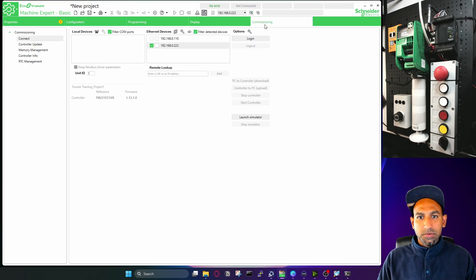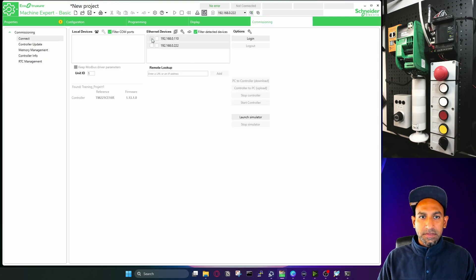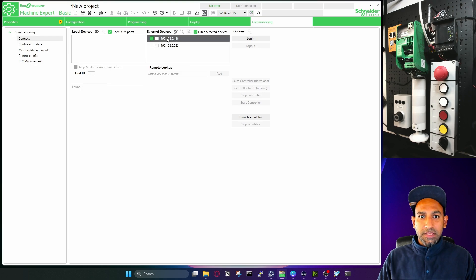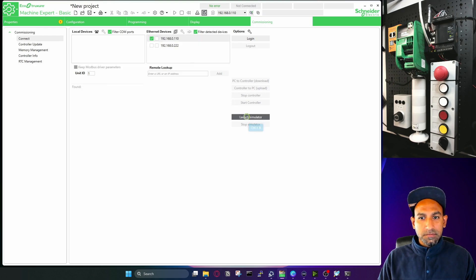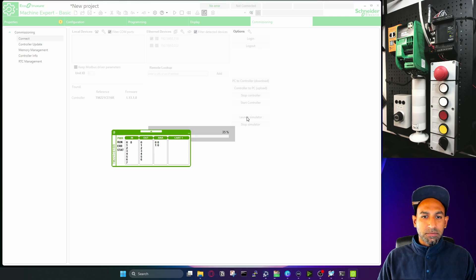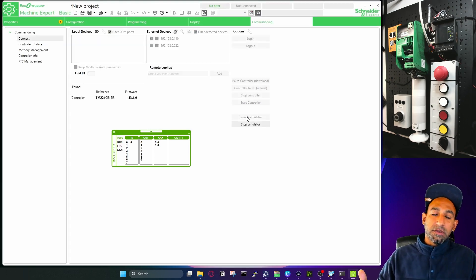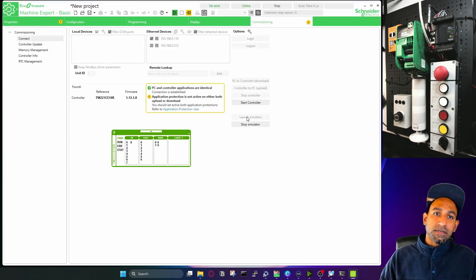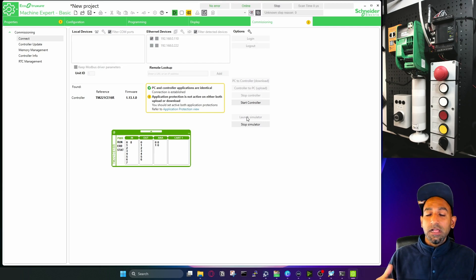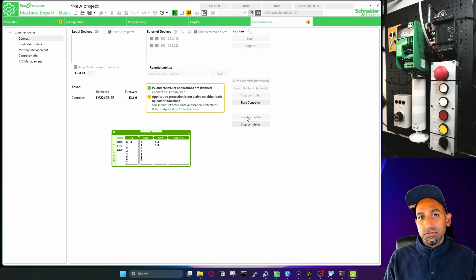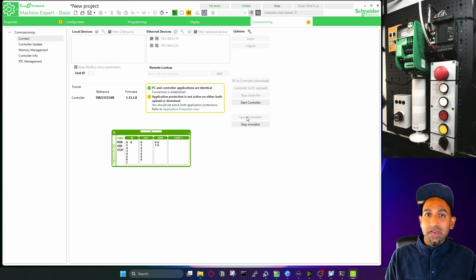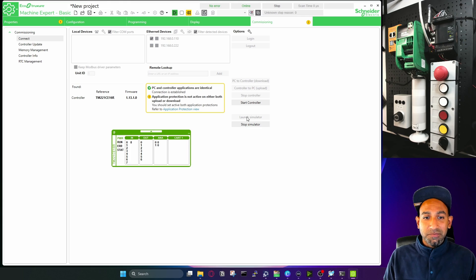Go back to commission. And I will see another IP address is coming. Select that one. And having that selected, click on launch simulator. So this will launch my simulator. And why did I put the IP address of my Ethernet card? Because it will help you to do Modbus communication with the simulator without real PLC, which is a game changer.